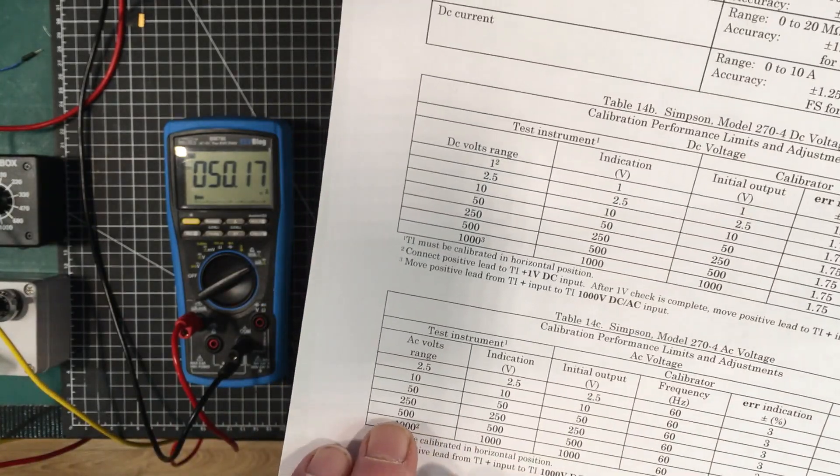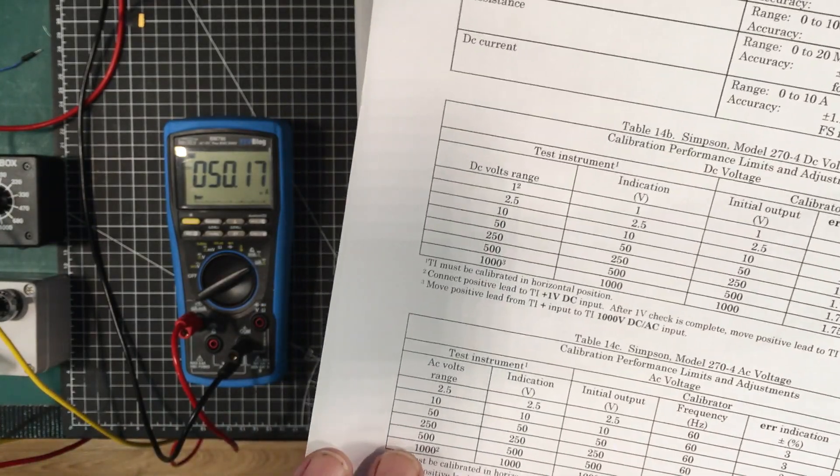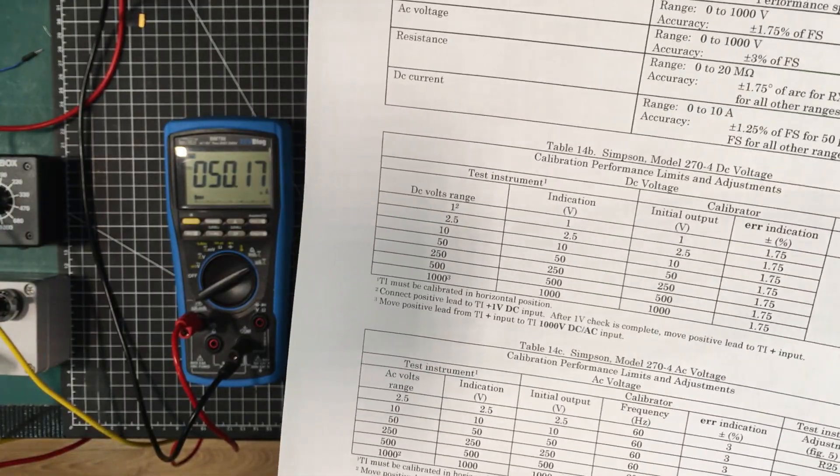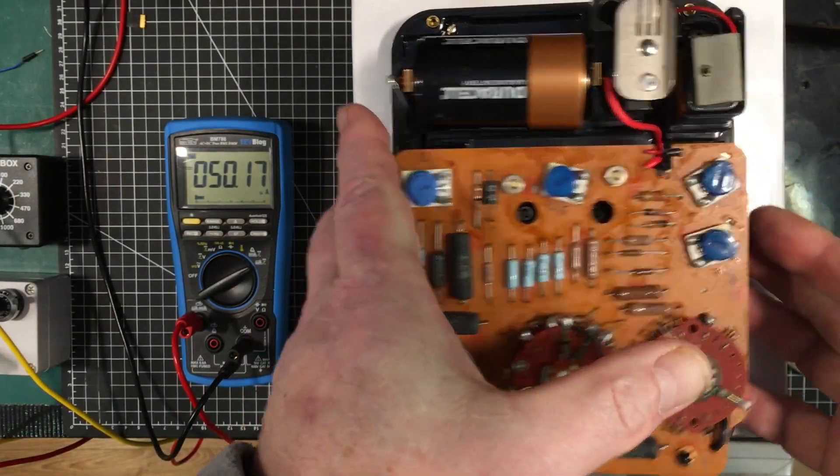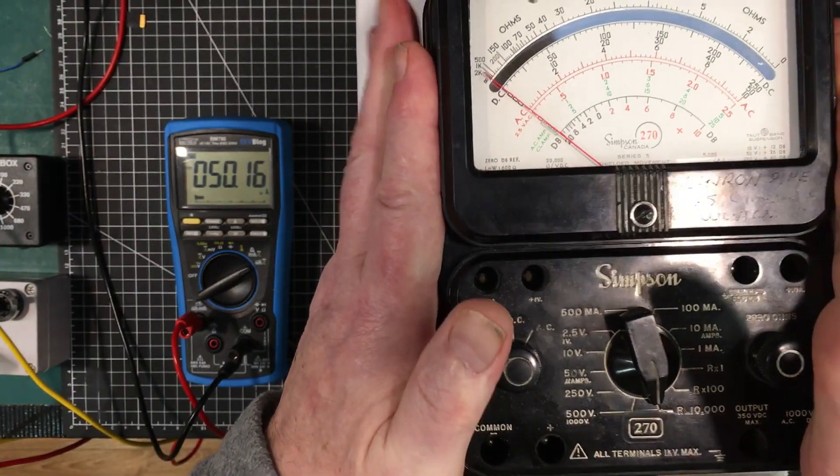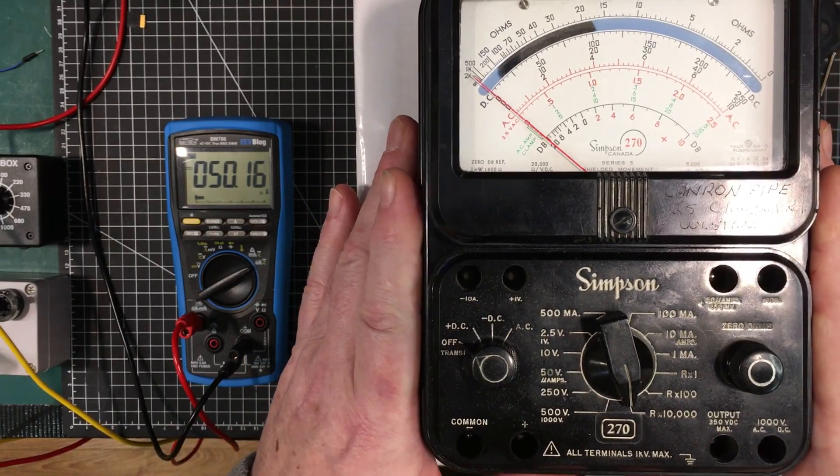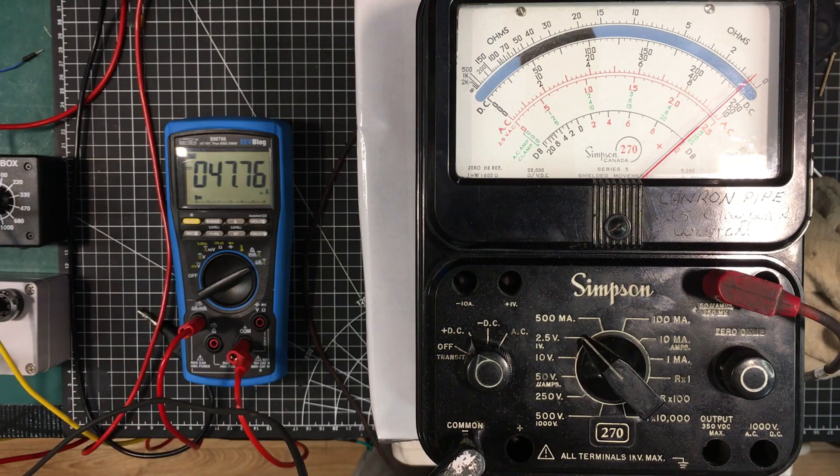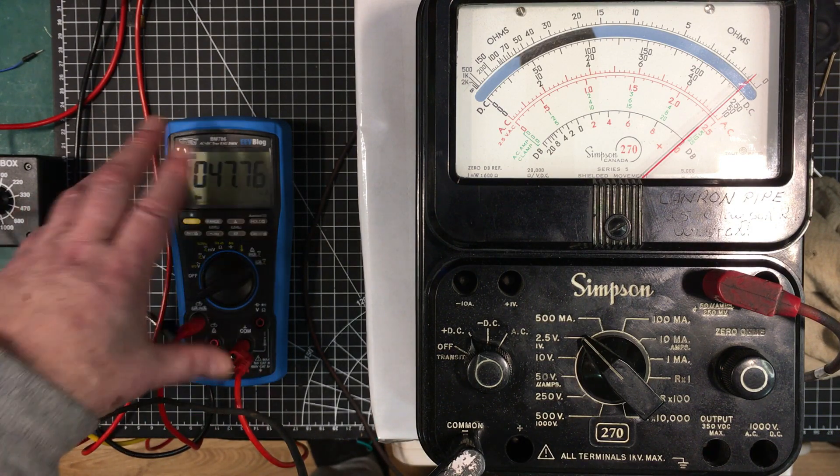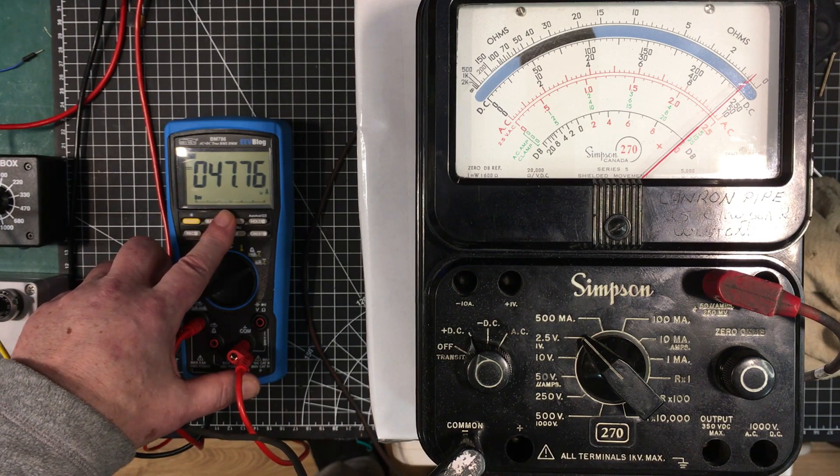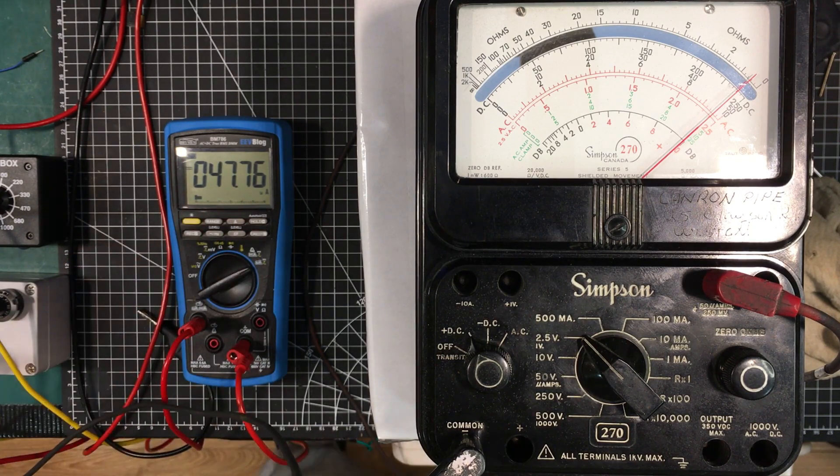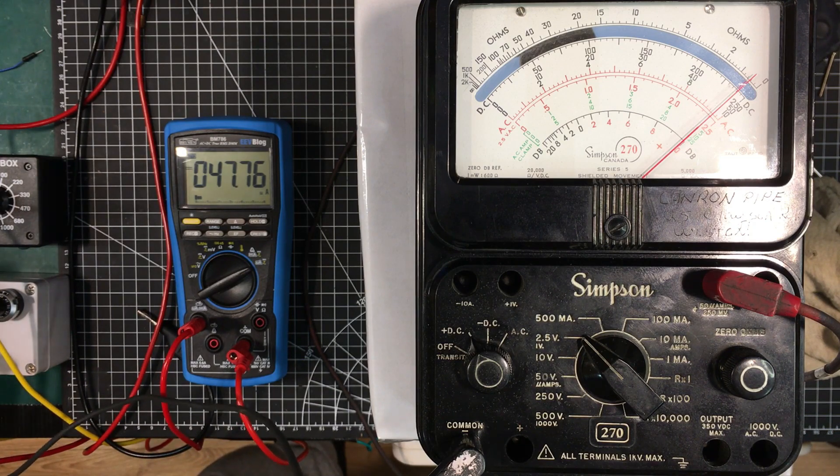Then we'll go to the AC. I'm going to use my Siglent waveform generator to produce the lower voltage R25 adjustment, and then we'll just use the mains for R22. Let's get the bottom on the thing and start checking it out.